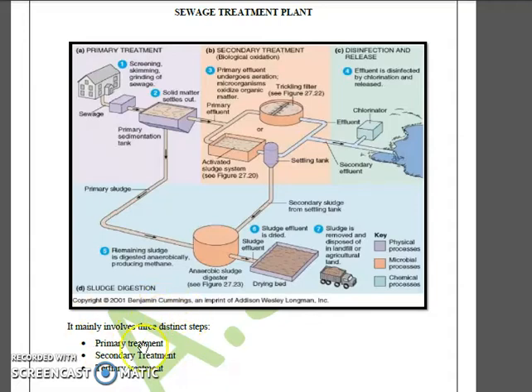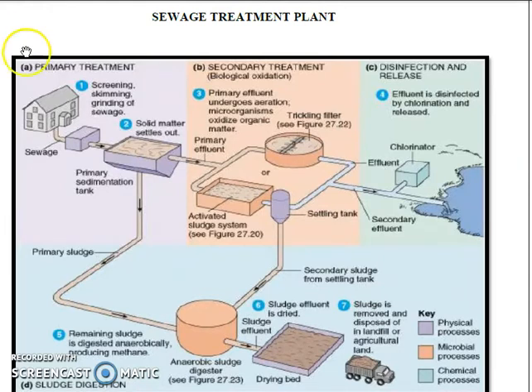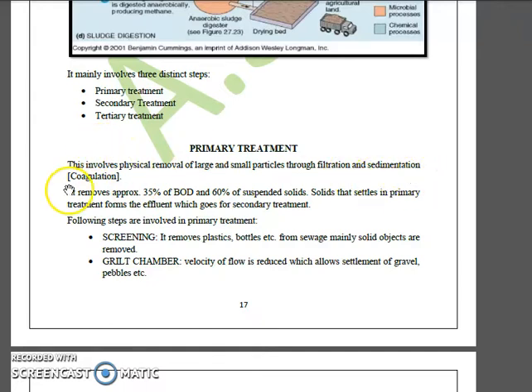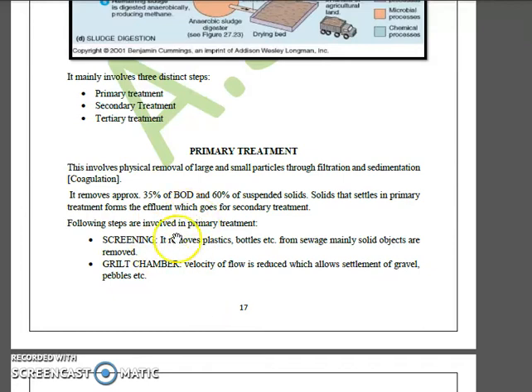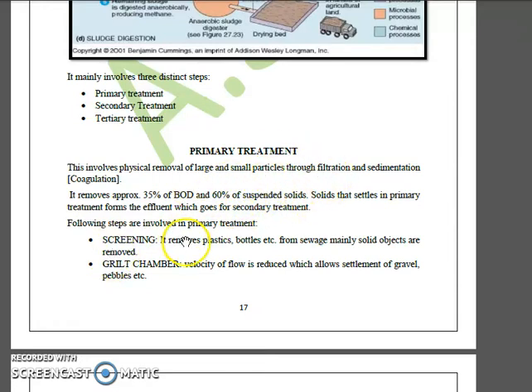Starting with primary treatment — this involves physical removal of particles, both large and small, through filtration, sedimentation, and coagulation. It removes nearly 35% of the BOD and 60% of the suspended solids from the wastewater. The solids that settle in primary treatment form primary sludge, and the supernatant forms effluent, which is then passed into secondary treatment.